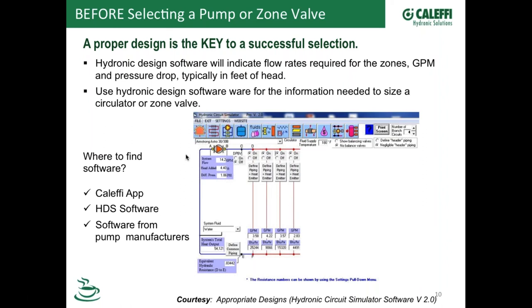And one of the places that I'll caution you about that is with some of these new high efficiency modcon boilers, some of those with the small tube heat exchanger, it takes a lot of pump to just circulate through the heat exchanger on those tube type of boilers. So you might have a high head pump required just to circulate through your boiler, through your primary, secondary hydraulic separator. But on the distribution side, you might be able to get away with a couple small pumps on speed one even.